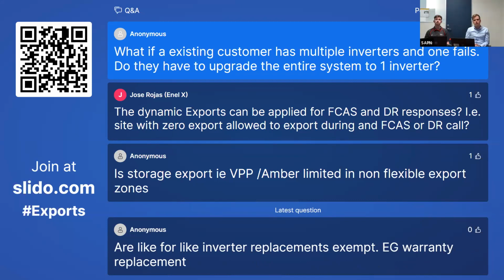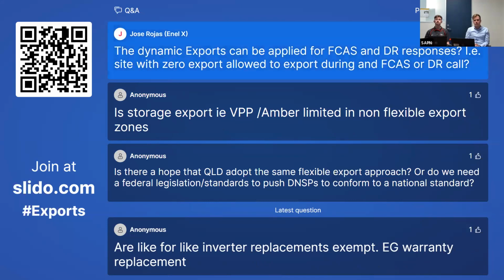Can dynamic exports be applied for FCAS and DR responses, with sites at zero export allowed to export during an FCAS or DR call? Typically sites responding to FCAS or demand response are battery systems, which are currently exempt from the requirements, so they can still have a 5 kilowatt fixed export limit, effectively exempt in the short term. We'll be working through how FCAS and demand response schemes fit in with flexible exports as we work towards the requirement for battery systems to be included in the scheme from March 2024.